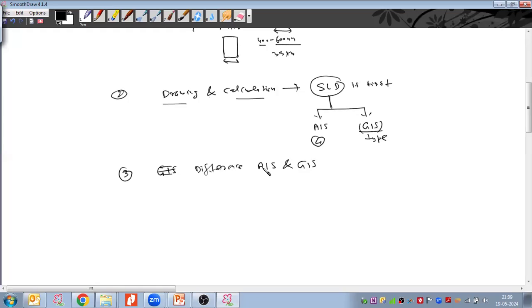In the AIS, the equipment is air insulated switchgear. Between the equipment, air works as an insulating medium. But when it comes to the GIS, gas works as an insulating medium. So we discussed what GIS is. GIS is a compact assembly of the switchgear, or we can say a compact assembly of the equipment. Which equipment? Like the disconnector, breaker, CT, VT, all the equipment that we use in the substation.